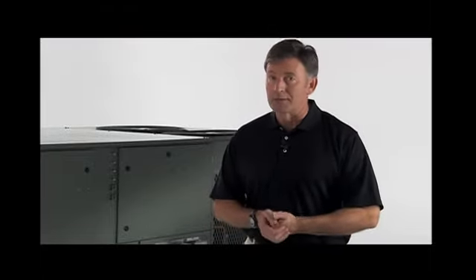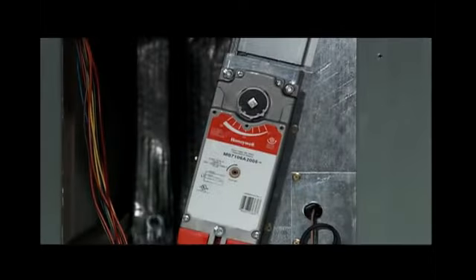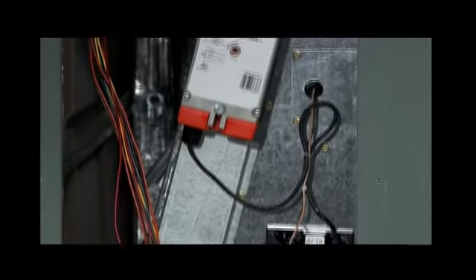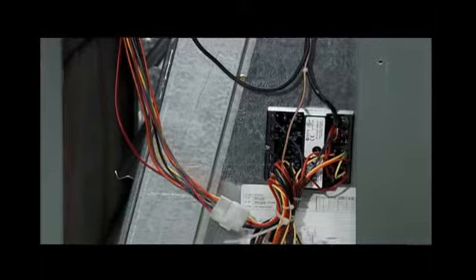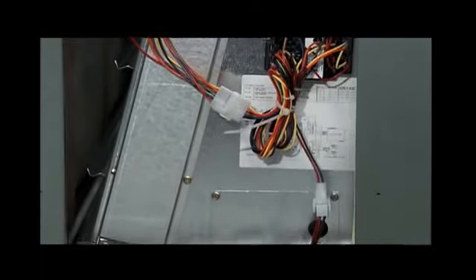The scroll compressor is known for its long life and for reliable, quiet, and efficient operation. The suction and discharge lines are designed with shock loops to absorb the strain and stress that the starting torque, steady state operation, and shutdown cycle impose on the refrigerant tubing. Each unit has 2 stages of efficient cooling operation. First stage is approximately 50% of second stage. 6 and 7.5 ton units are single stage cooling.